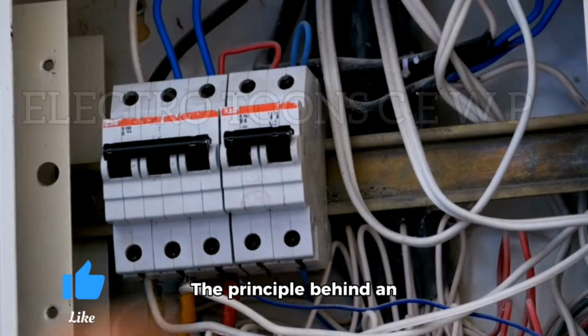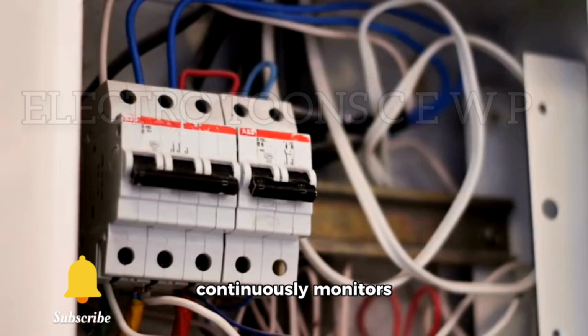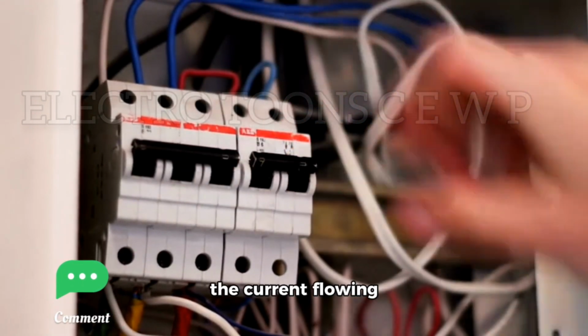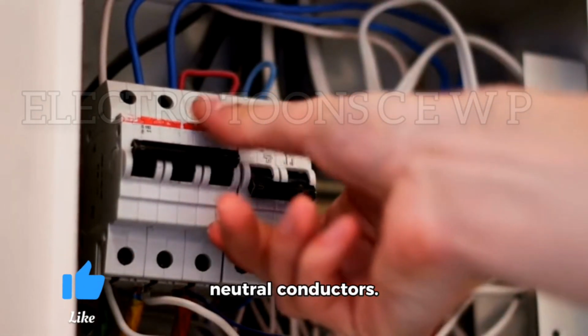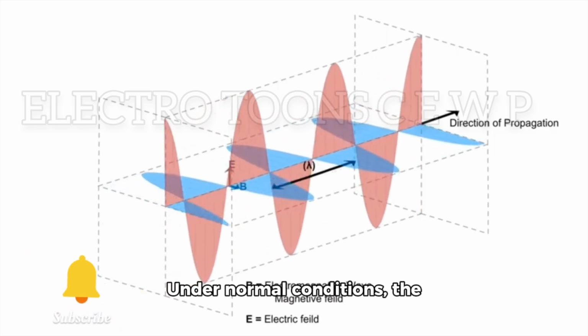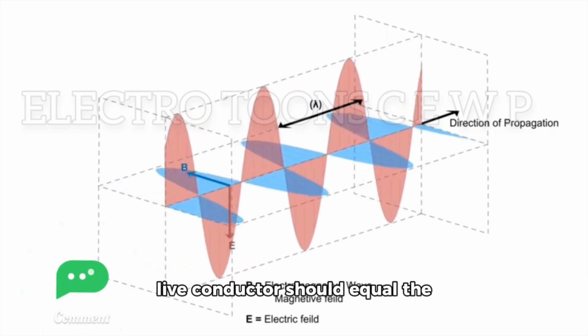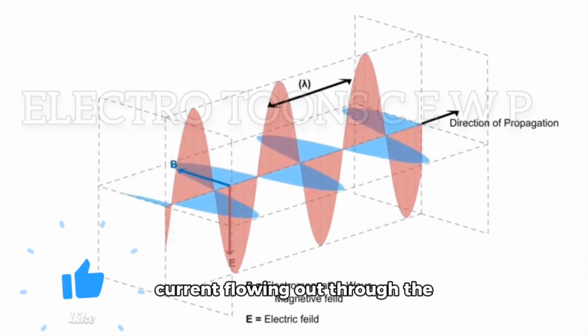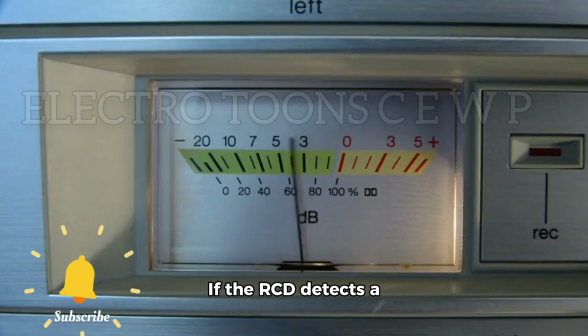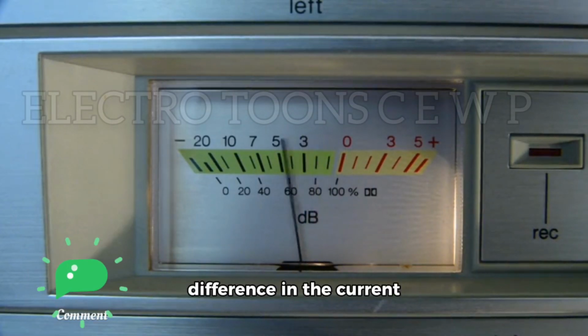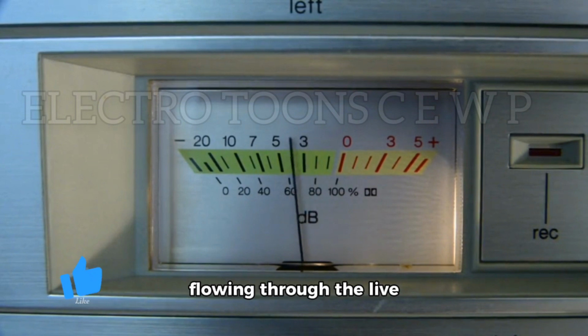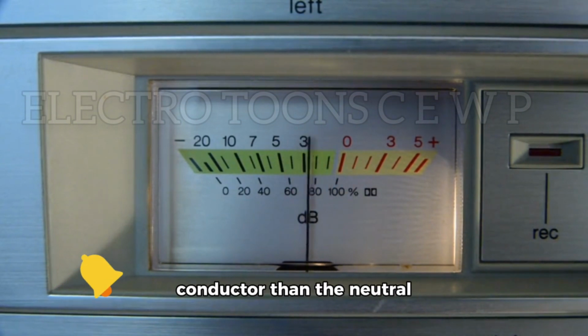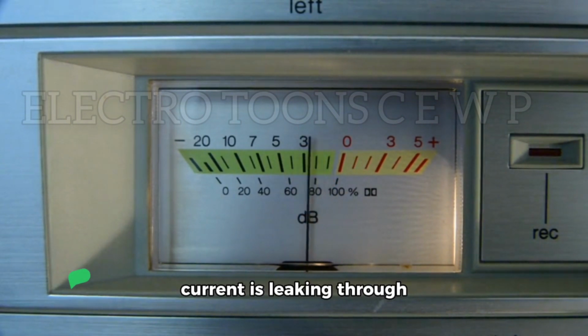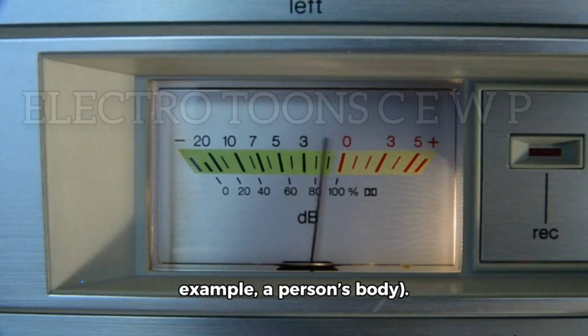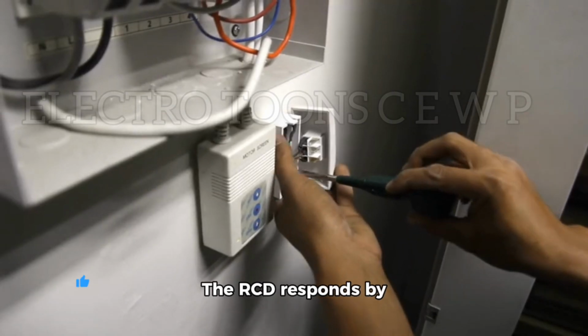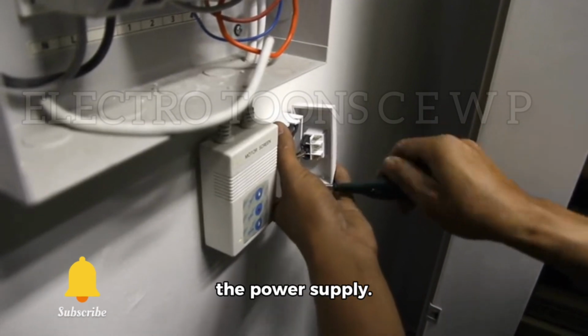The principle behind an RCD is fairly simple. It continuously monitors the current flowing through the live and neutral conductors. Under normal conditions, the current flowing in through the live conductor should equal the current flowing out through the neutral conductor. If the RCD detects a difference in the current, meaning more current is flowing through the live conductor than the neutral conductor, it assumes some current is leaking through an unintended path, for example, a person's body. The RCD responds by quickly disconnecting the power supply.